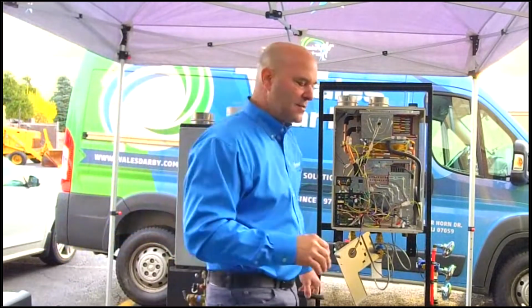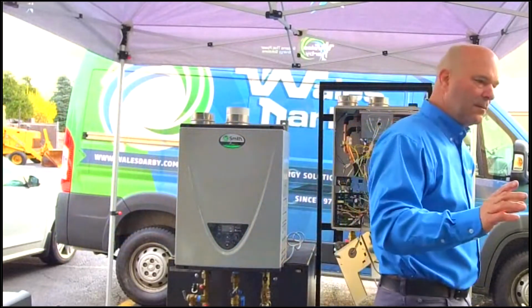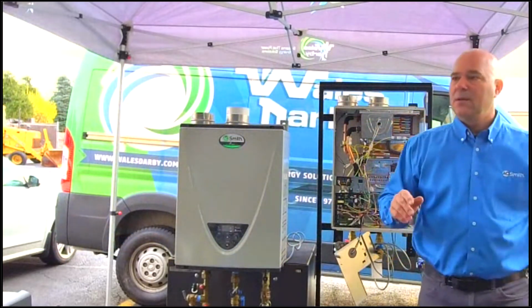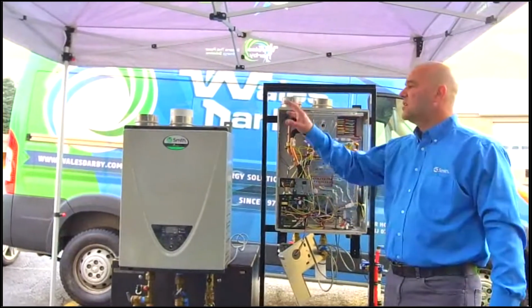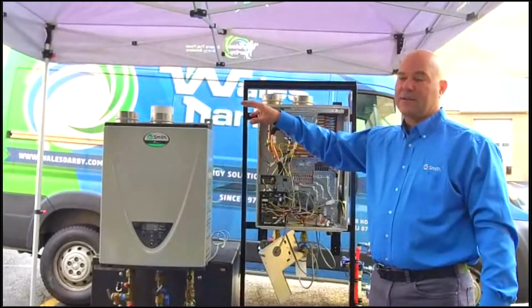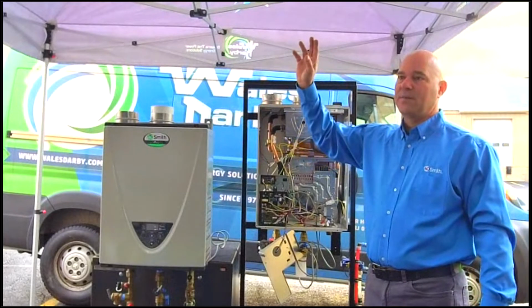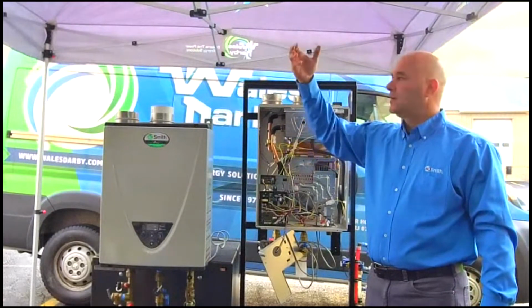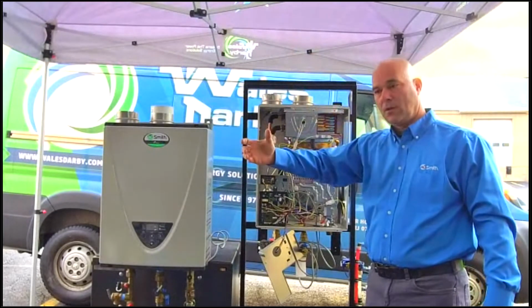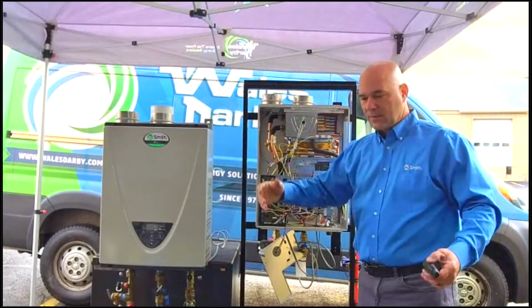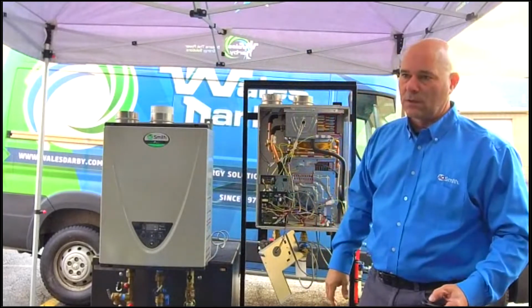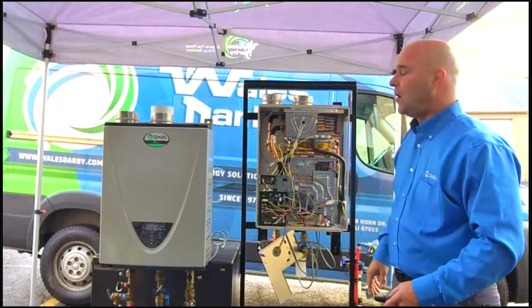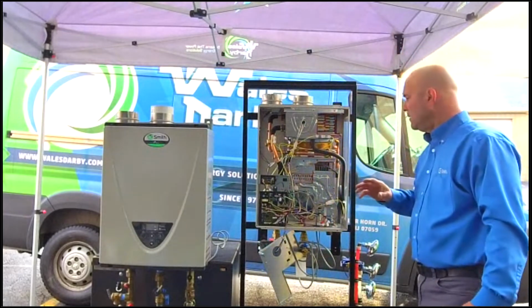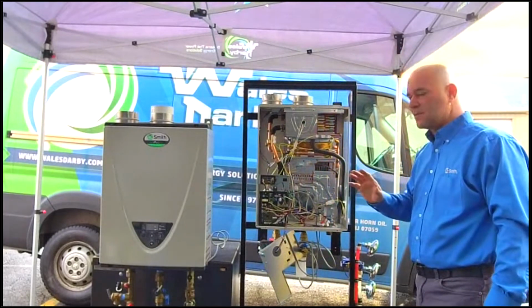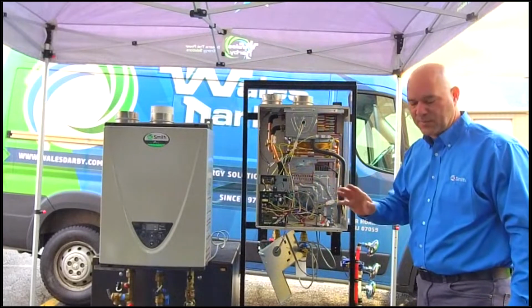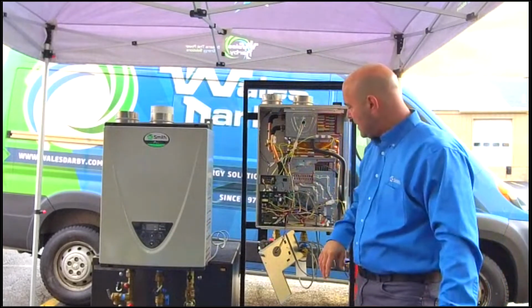Different termination options. Go to the manual based on your installation. Take a look at your installation, see what it's going to look like, see where your vent terminations need to go, whether it's going to be straight up through the roof. You're going to leave your vent straight up. You're going to snorkel over your air intake. It'll depend on the installation, what it will look like. So venting is key. Please pay attention to venting.